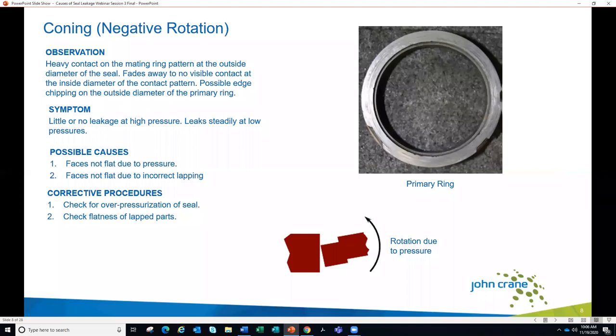The first topic we're going to look at is what we call coning, also called negative rotation. As you can see in the diagram, we have the mating ring on the left and the primary ring on the right. We're seeing heavier rotation, most likely caused by pressure, causing higher contact at the OD of the faces. Because of the narrow profile of the mating ring, you might see some edge chipping occurring at the OD of the primary ring as well, with heavier wear at the OD and potentially no contact toward the ID depending on the amount of distortion.